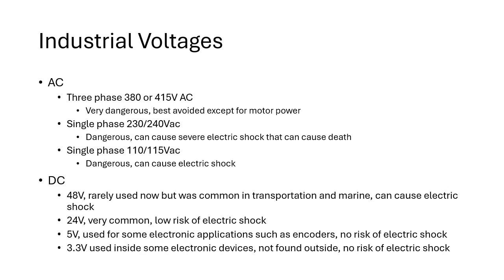So DC, 48 volts used to be quite common. I used to see it a lot in transportation applications and marine applications. 48 volts DC, although it's not that high, can still cause an electric shock. That's high enough to overcome your skin resistance, and it may not be fatal, but you can still certainly feel it. So these days we've reduced the standard voltage to 24 volts. As I say, that's the standard under the machinery directive. And now what you'll find is, unless you've got very wet skin, generally your skin resistance is high enough that you wouldn't feel a shock from 24 volt DC. Because it's a lower voltage, we do need thicker conductors though. So in some applications you still have 110 volt or higher voltages, because otherwise, with a 24 volt connection, the thickness of the cable would just have to be too thick and too expensive.